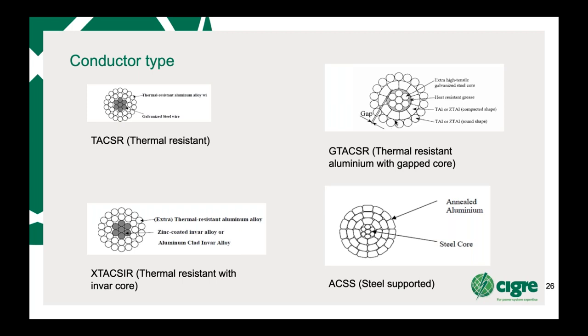Or you could use what is quite common in the US, an ACSS conductor, which is steel supported. So this here is entirely annealed. So you can go up to 250 degrees with a conductor which costs about 20% more than a normal ACSR, and you can use the same hardware. Whereas with these others, you need to be careful in using hardware, and the gap is a very complicated conductor to actually join.